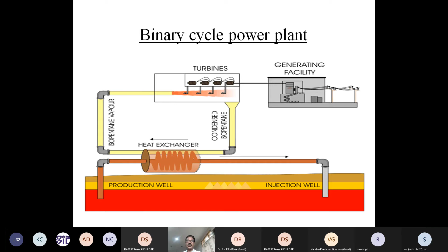It does not use steam directly to spin turbines; only the heat of the underground water is used. Vaporized hydrocarbons are used to spin the turbine. Hydrocarbons having low boiling points such as isopentane, isobutane, and propane can be used. No harmful gas is emitted to the atmosphere because the underground water is never disclosed to the outside, since there is a heat exchanger - the heat transfer happens indirectly. So that's the worldwide accepted power plant.